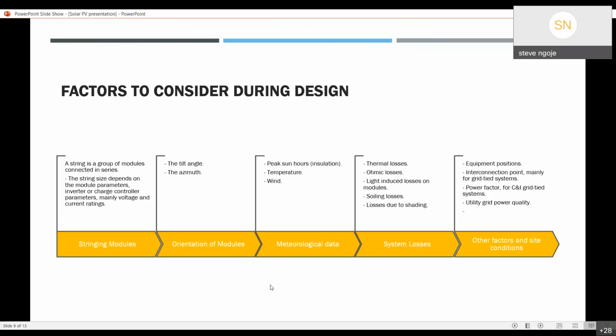But again, ohmic losses, back to voltage drop. It depends on which company and also country, but it's always good to have. Some will tell you 1.5. Some people will tell you they need 2% maximum voltage drop. Some people will tell you they can go up to 3%. So again, as a designer, you need to understand which client you are designing for and what their requirements are, but also generally you have to be aware of the Kenyan laws about voltage drop.